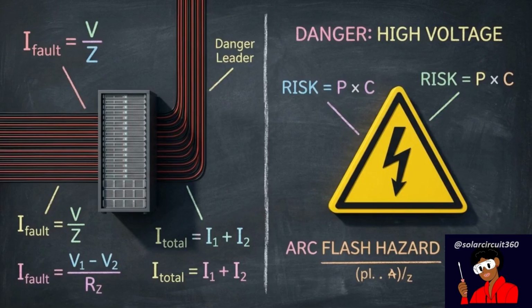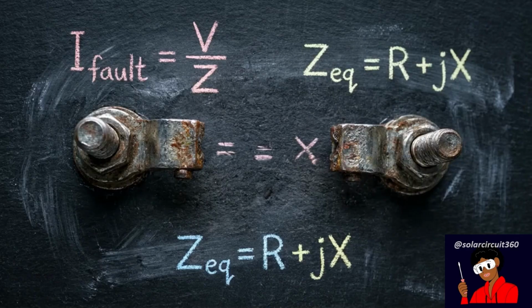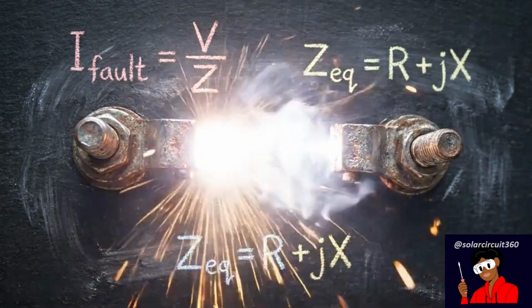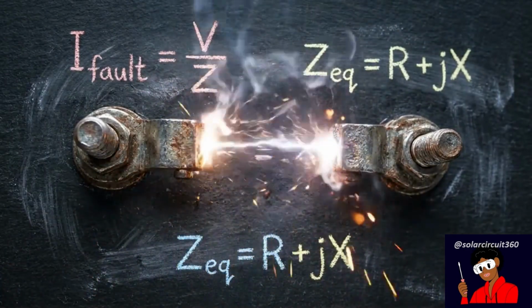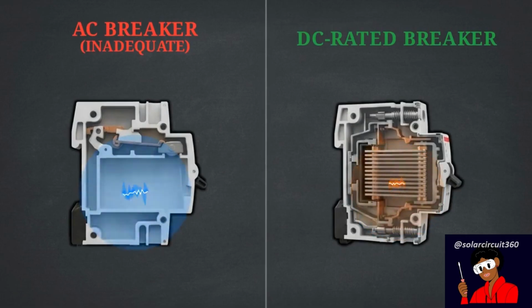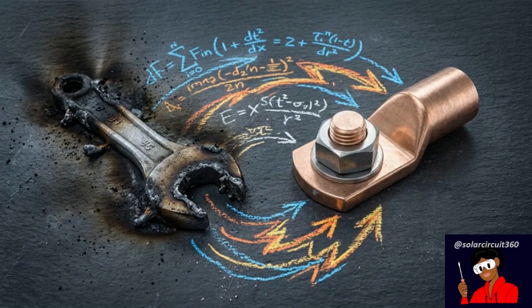While 48-volt systems simplify continuous current management, they simultaneously increase the severity of potential fault currents. A dead short in a large 48-volt series battery bank can instantly deliver thousands of destructive instantaneous amps. Standard AC-rated breakers are utterly useless in this scenario. They lack the specialized magnetic chutes required to extinguish sustained high-voltage DC arcs. Loose torque specs or an unbalanced battery management system in a series configuration can cause cascading failures that vaporize hand tools in milliseconds.